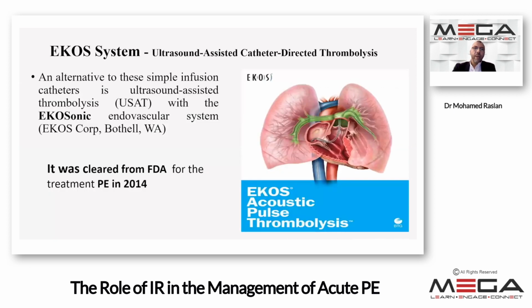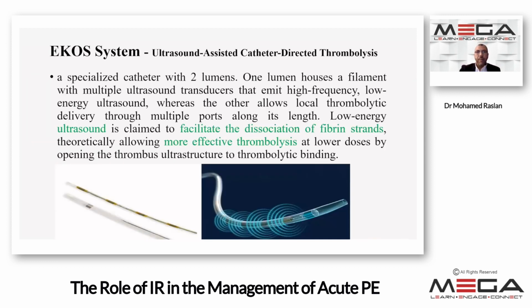So going now to the EKOS. As an alternative to the simple infusion catheter, this is an ultrasound-assisted thrombolysis with the EkoSonic endovascular system from EKOS Corporation. This was cleared by the FDA, as we said, in 2014. So it's a specialized catheter with 2 lumens. 1 lumen houses a filament with multiple ultrasound transducers that emits a high frequency, low energy ultrasound, whereas the other one allows local thrombolytic delivery through multiple ports along its length.